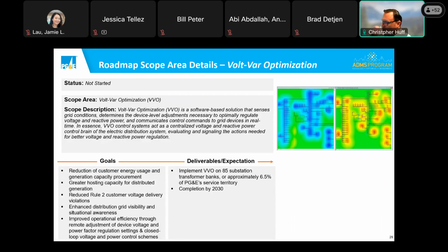I want to focus on volt-var optimization. Today feeders have various different volt-var optimization assets on them. They have LTCs, or load tap changers. They have voltage regulators that sit at the substations, as well as on the distribution feeders, and capacitor controllers that can also be at the substation or on the feeders. Today, these devices operate and resolve volt-var and support voltage at their individual locations, solely based on what they can sense at their specific sites.